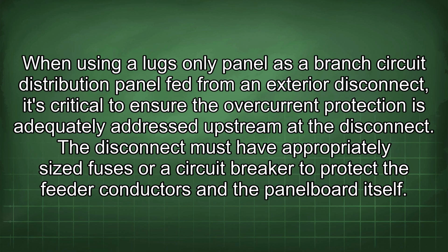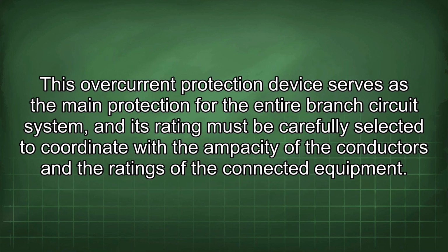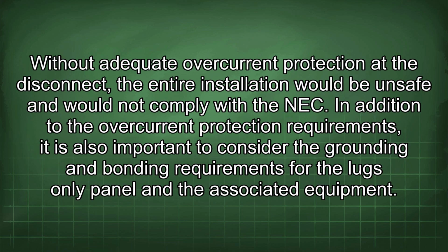When using a lugs-only panel as a branch circuit distribution panel fed from an exterior disconnect, it's critical to ensure the overcurrent protection is adequately addressed upstream at the disconnect. The disconnect must have appropriately sized fuses or a circuit breaker to protect the feeder conductors and the panel board itself. This overcurrent protection device serves as the main protection for the entire branch circuit system, and its rating must be carefully selected to coordinate with the ampacity of the conductors and the ratings of the connected equipment. Without adequate overcurrent protection at the disconnect, the entire installation would be unsafe and would not comply with the NEC.